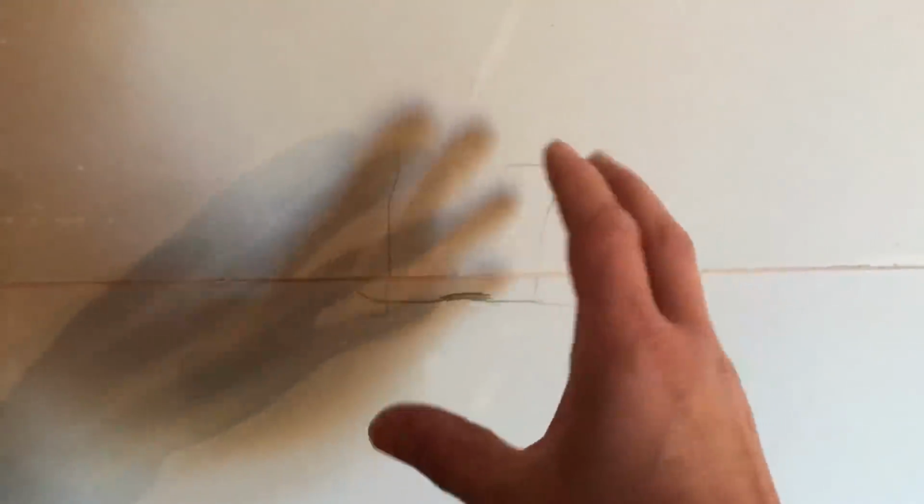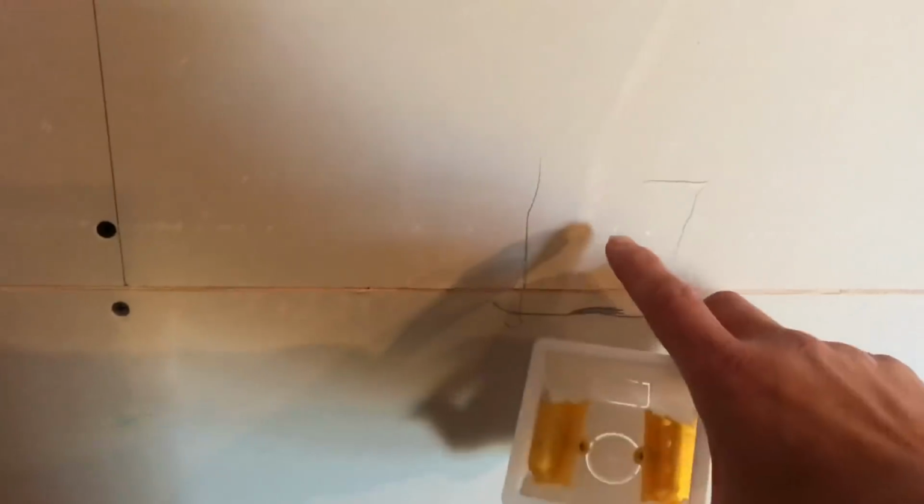So as this is a butcher shop, they've got an oven here. I think they cook bread and stuff. So we've got to put a 6mm feed to here, but they can't have anything at 1200. So obviously you'd have a normal cooker isolator here. So what we're going to have to do is mount the cooker isolator below the fuse board that's going up here. We'll have a cooker isolator here. They're not allowed anything at 1200 because it's infection control malarkey in a butcher shop.